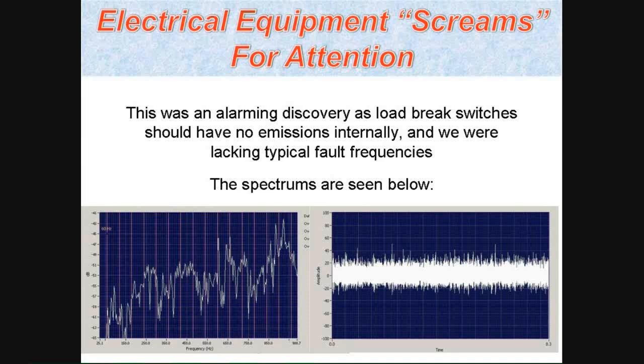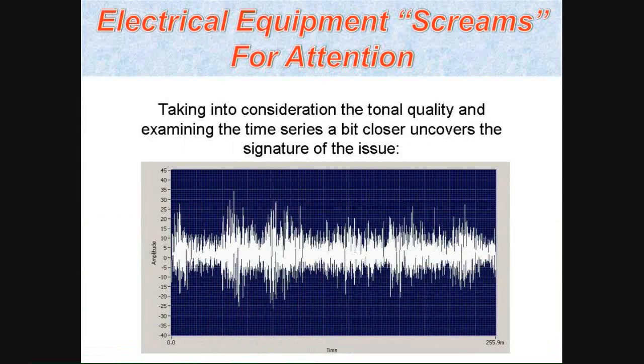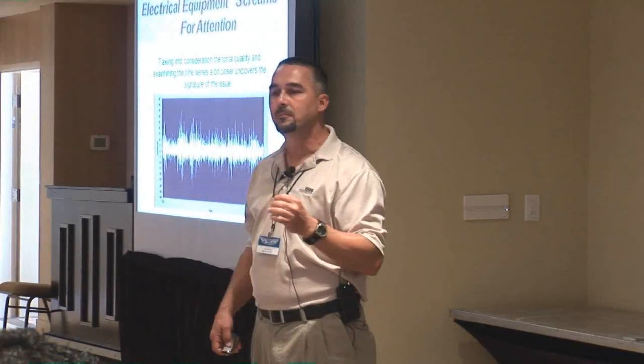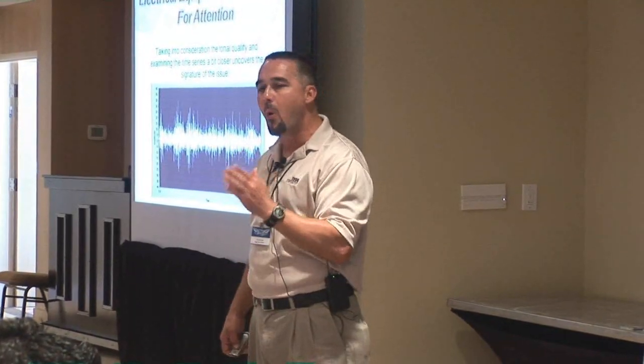So looking at these two side by side, and unfortunately you couldn't hear it, the one thing about the time domain electrical, you have that band of white noise throughout, and if there's any discharges going on, you'll see these spikes or excursions throughout that spectrum. And that's somewhat evident, but you have to slice and dice it, to use Mark's term, to really take a peek inside. What we're looking at here is variations in between the amplitude of those discharges, as well as variations within the spacing between it, meaning the timing. And that tells us two things: there are discharges occurring, and there's no pattern relative to the electrical sine wave on when that's occurring.